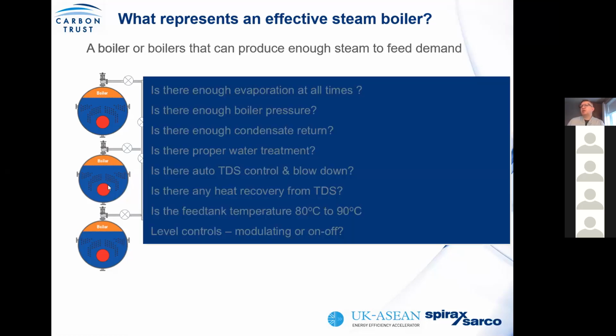So let's look at your steam boilers. Is there enough evaporation at all times? What that means is, can the boiler generate the steam at the rate at which it's being consumed? Or do you find that you have what we call steam starvation or pressure decay? What that means is some end users are struggling to achieve temperature if, for example, another process comes on. So in other words, how do your boilers operate in response to matching your pressure?